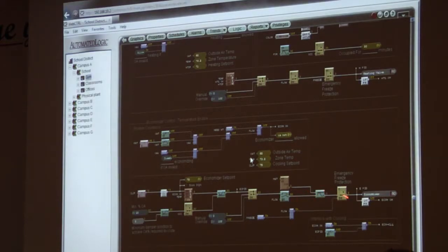Why doesn't this 20 go through? Well, apparently they're all merging right here. So without a doubt, I know which microblock. Even though you've never looked at it before, you know which one to click on to start to look for your problem, all right? We're going to take a look at this microblock, say, yep. And if I go back here, look, 20, 20, 20, 20, right? It's going all the way through. So right about here, that 20 is becoming a 0. Let's find out why.